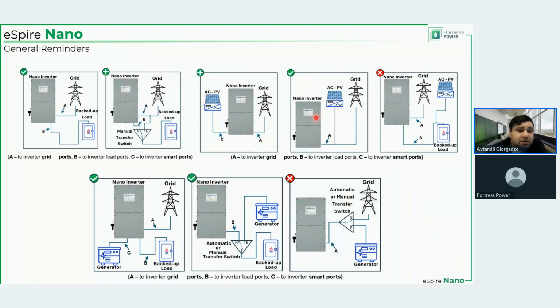You can also have, and in this case, obviously, AC coupled PV will be available even if the grid is down. You can also connect AC coupled PV upstream of the inverter grid ports, in which case that PV will be lost when the grid is lost. What is not allowed, as I said before, is that you cannot have grid connecting to the inverter and, on the load port side, downstream of the load ports of the inverter, having AC coupled PV connected. This is not allowed.